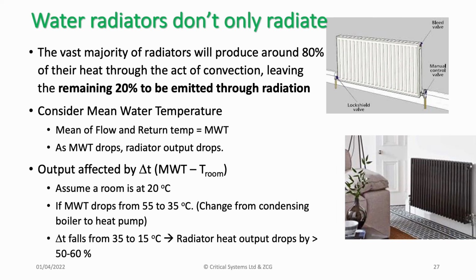So if I was to look at a change from a condensing boiler to a heat pump system, the delta T between the mean water temperature and the room falls from 35 to 15 degrees C, and the output of a radiator could drop by 50 or 60%. So you can see why generally you need a much larger heating surface. You may be lucky in your property that the radiators are oversized, but this needs very careful evaluation.